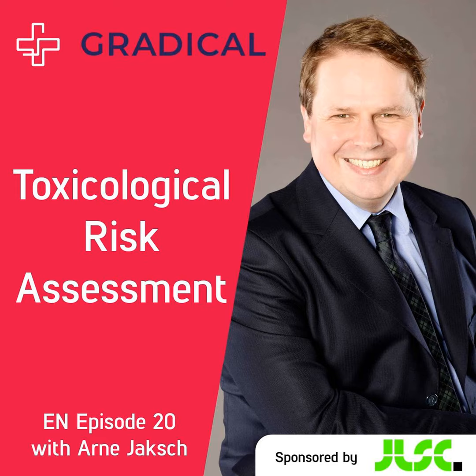Yes. Okay, so walk us through a toxicological risk assessment, how you would perform that. What steps would you take in order to create a good database for doing that? Well, to establish a good database for a toxicological risk assessment, there are many steps which must usually be taken. This also depends a little bit on the life cycle of the device, so in which phase we are. But usually, like you mentioned already, the intended purpose, indication, contraindication, contact classification, so type and duration of contact, the patient population, this must be defined or should be known at least. And then, of course, for the patient population, you need to include possible risk groups, and those possible risk groups must also be determined.